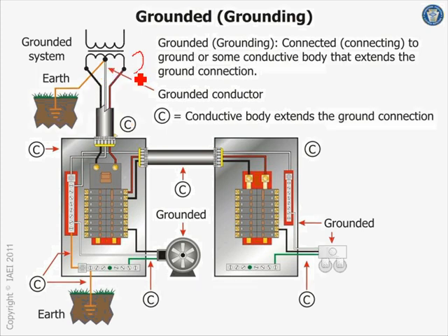is a 220 system like they use, here's my 220 system. Now imagine this conductor does not exist, the second leg here does not exist. So now you brought your neutral to this point, and this does not exist at all. You still have to do everything else. You're creating a grounding electrode conductor and a grounding electrode bar, and all your grounds are coming here. The only thing that does not exist is that system bonding jumper. You can't do it. Does that make sense?